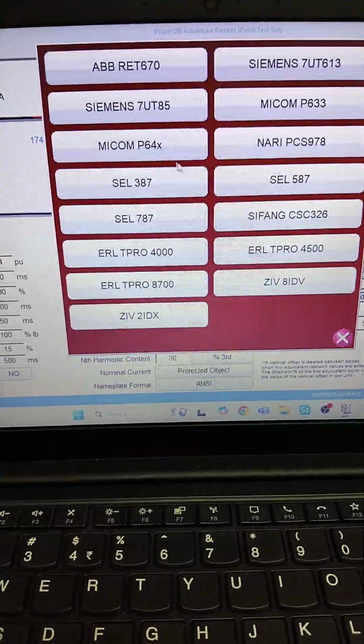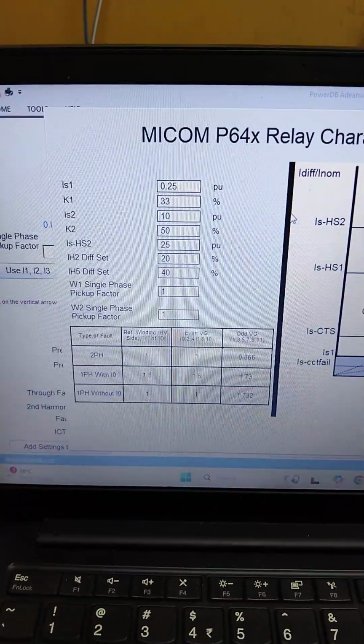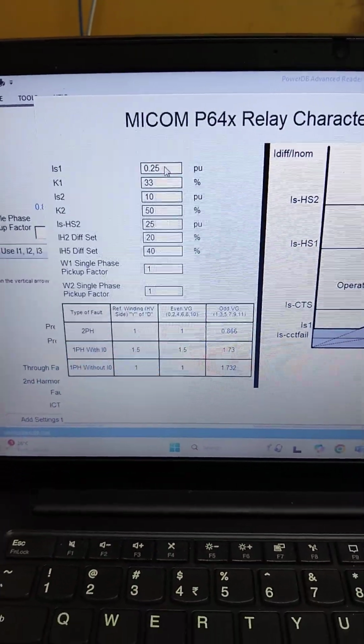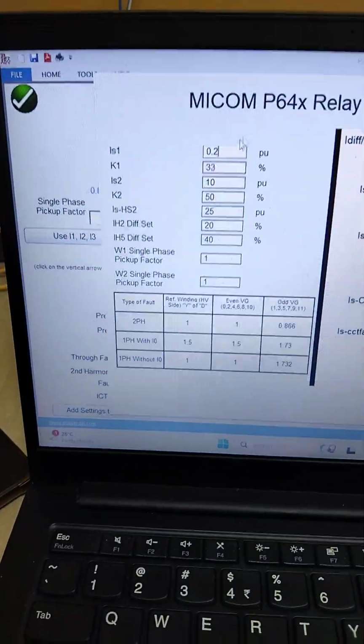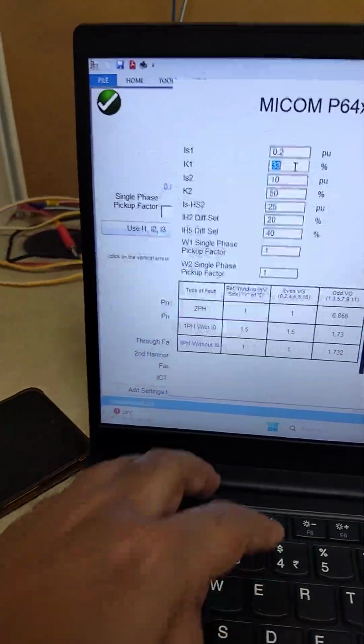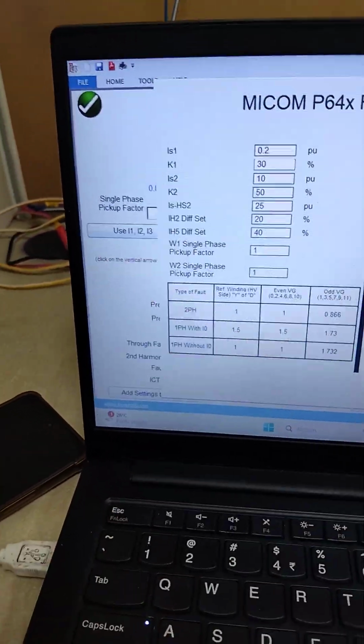Just go on to this bookmark icon and select the P64 template. So you will get what you see in the relay itself. So now IS1 in our relay we have entered as 0.2, the pickup value. First slope is 30%, so change it to 30%.